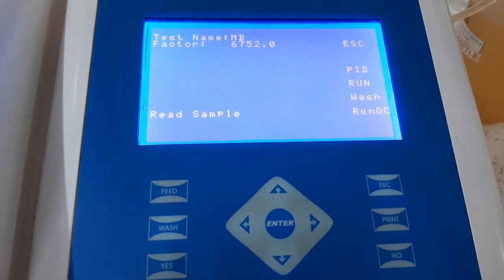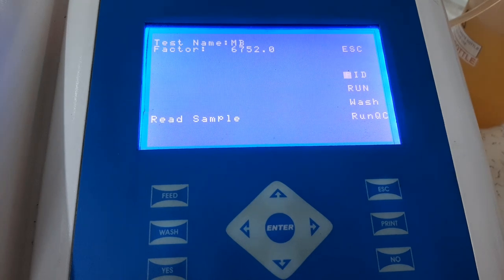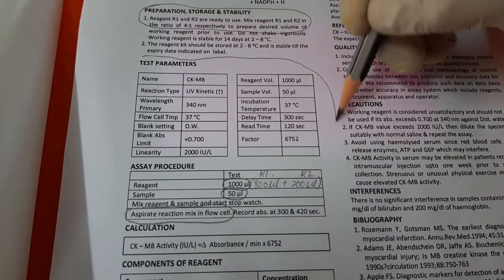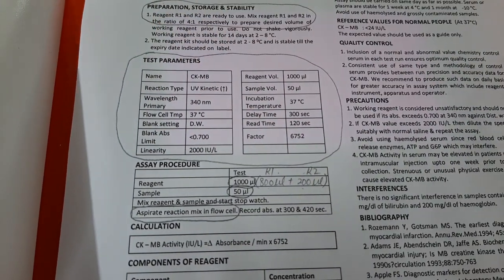Before addition of the sample, make sure that you have switched on the instrument and opened the program of CKMB. Please refer to a separate video in which we have explained how to program CKMB kit on any semi-automated biochemistry analyzer using the parameters mentioned in the instructions for use.